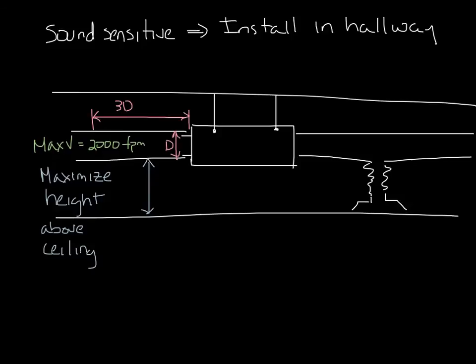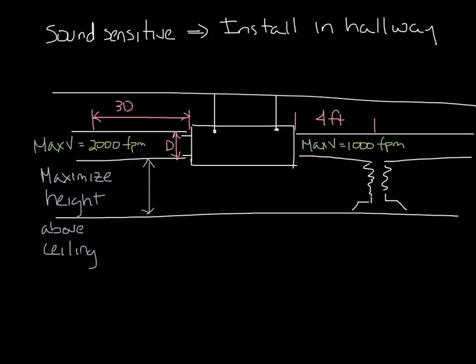So now moving on to the discharge of the box. You should keep your discharge velocity under about 1,000 feet per minute. And you want a minimum of 4 feet of lined ductwork before you drop to any diffusers. And you'll want to use about 4 or 5 feet of flex duct to each diffuser, installed as I described in the Diffuser Inlet Effects podcast, of course. So these guidelines should give you the lowest possible sound and best airflow conditions into your occupied space.